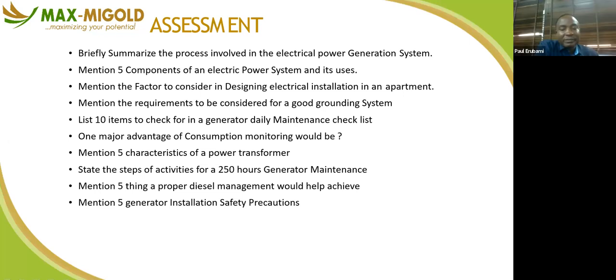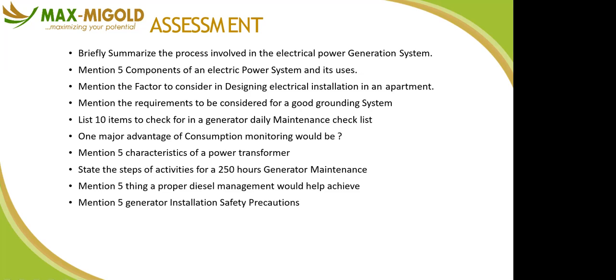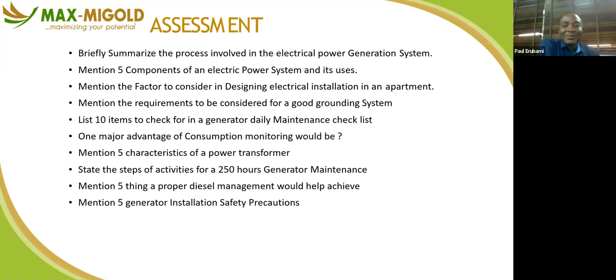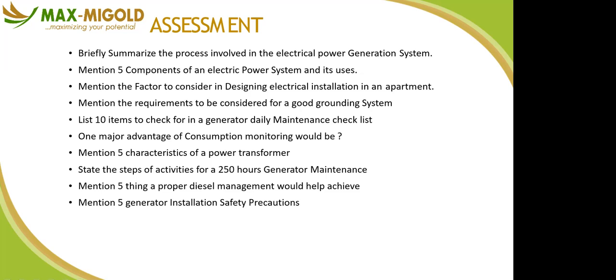Yeah, exactly. So what we did last week is we bought another 250 kVA, took away the 500 and put it in, but it's still underutilized, because people get there and just put on only one AC. They are not utilizing the power that has been calculated for the house. You get into somebody's house, he's just putting on the AC in his parlor and his fridge is running. Per month, when you read their both meters, they are not even getting to 100,000. And you are buying diesel. Diesel is now 380 or 360, as I'm talking. So I still feel that sometimes when we calculate, maybe we should look at the way the metering is. It helps us, because it was a lot of money.